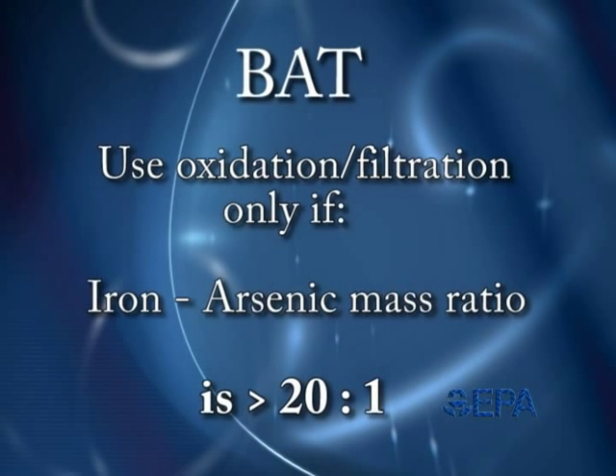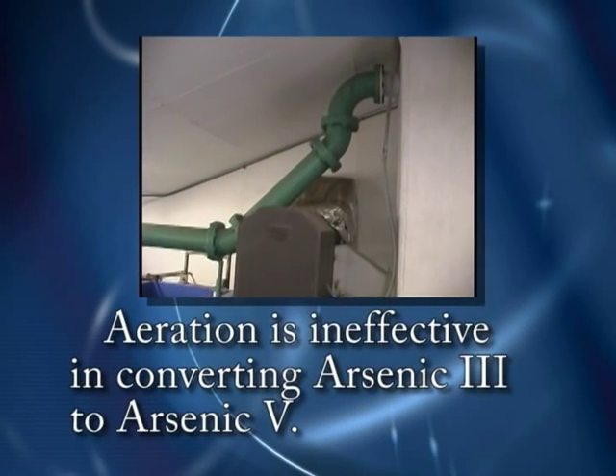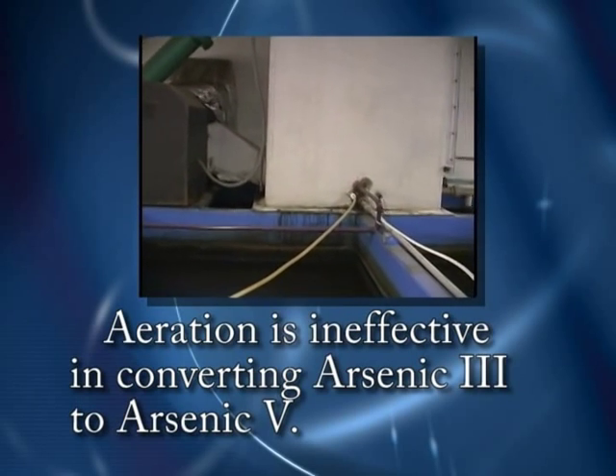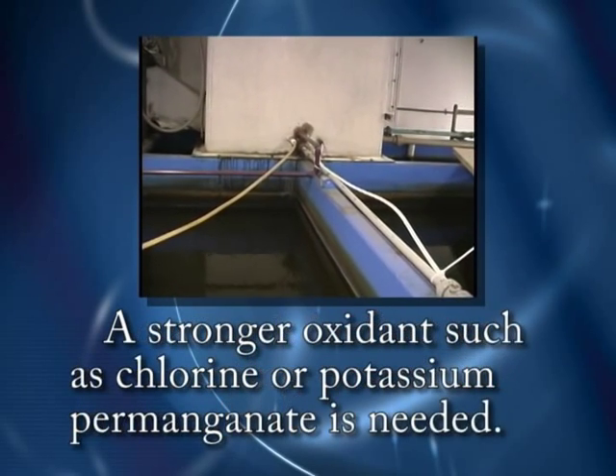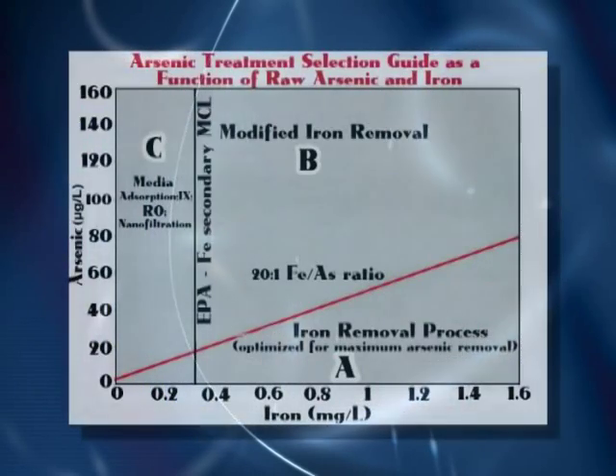EPA determined that oxidation filtration would be listed as a BAT only under the condition that the iron-to-arsenic mass ratio was greater than 20 to 1. This treatment method can be used to meet the revised MCL of 10 micrograms per liter. Aeration for iron oxidation has been shown to be ineffective at converting arsenic-3 to arsenic-5; a stronger oxidant such as chlorine or potassium permanganate is needed.